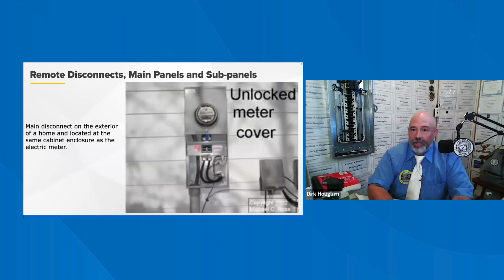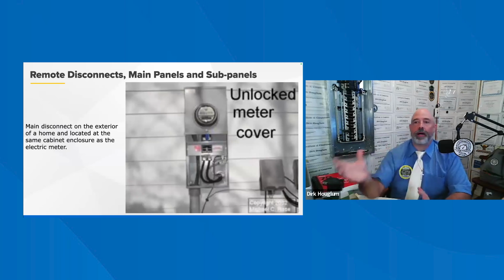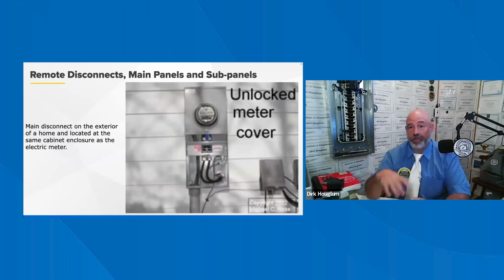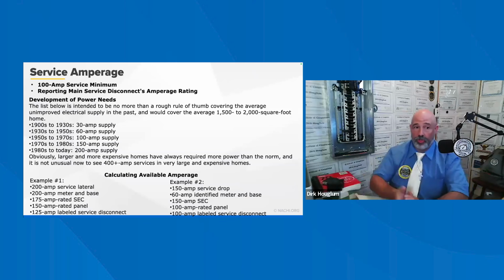In many homes, and in nearly all mobile or manufactured homes, the service disconnect is not in the main distribution panel. This is not a problem, but care must be taken to fully understand the grounding and bonding of all the downstream distribution panels. In terms of grounding and bonding, the neutrals and grounds should be bonded, connected. We've talked about this. Remember that the panel with the main disconnect is the service panel, and the panels downstream are the subpanels, or distribution panels. Neutrals and grounds should be bonded together only in the service panel. Remember that, and try to remember that throughout, depending on the year of the house, because that has changed over the years. It was acceptable years and years ago.